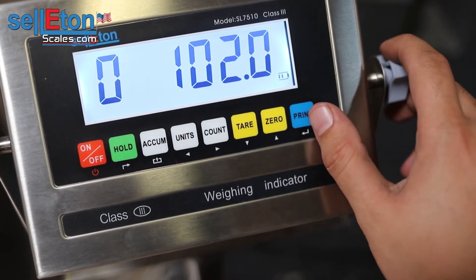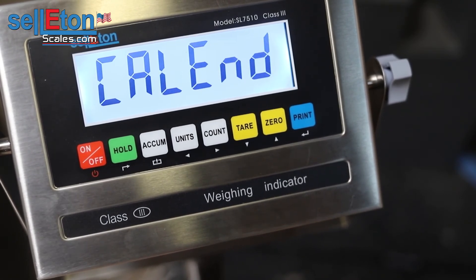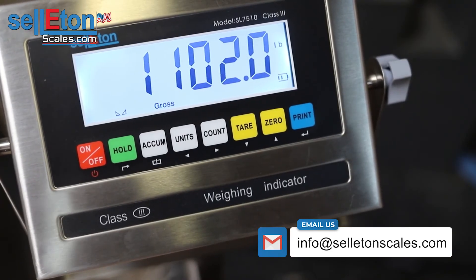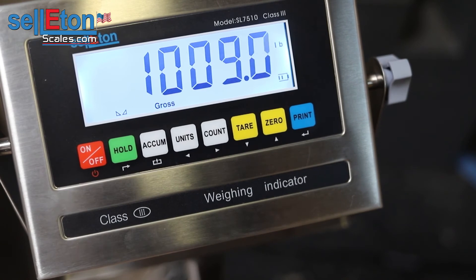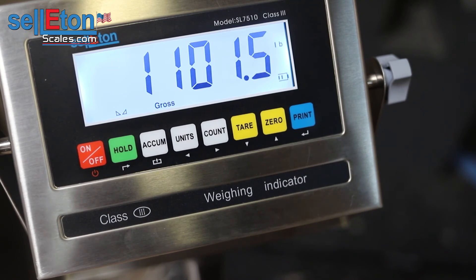I have the weight on the scale, so I'm going to press print. From here I'm going to press ACCUM and it will show that I have 1102.0 on the scale. I'm going to raise the weight and if you look on the side you'll see the numbers moving in 0.5 increments. I'm going to place the weight back down. 1102.0 — it is good to go.